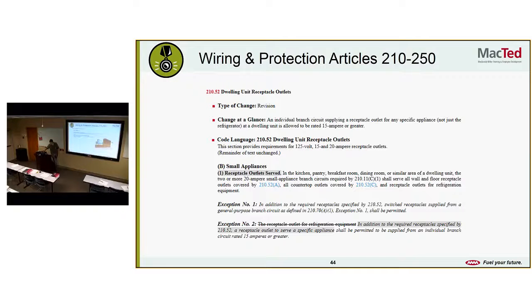Dwelling unit receptacle outlets. Revision. An individual branch circuit supplying a receptacle outlet for any specific appliance, not just the refrigerator, at a dwelling unit is allowed to be rated 15 amps or greater. So whenever you do a kitchen, you have to have two 20 amp circuits. They're considered small appliance circuits, but you can have individual 15 amp circuits in addition to those. Like for a dishwasher, a garbage disposal. So you can run more of that.